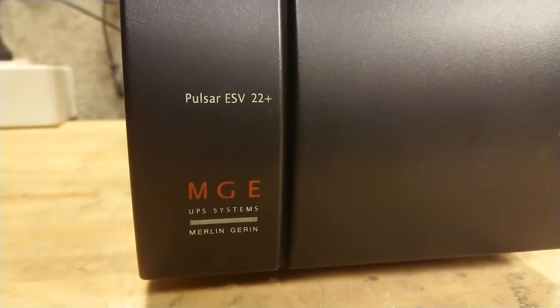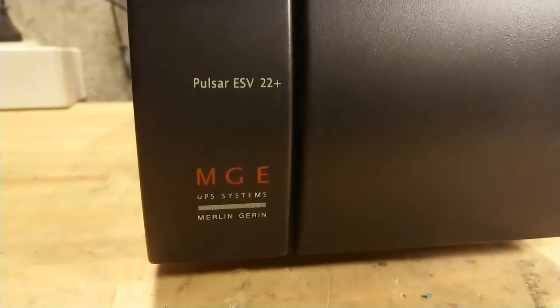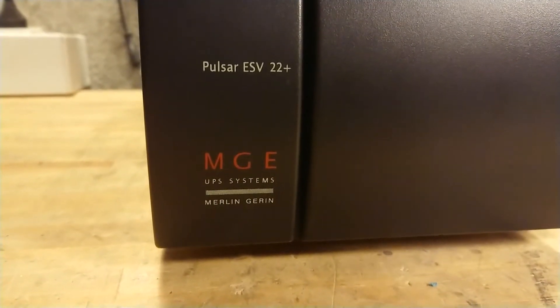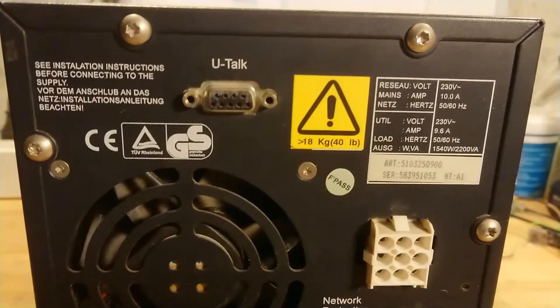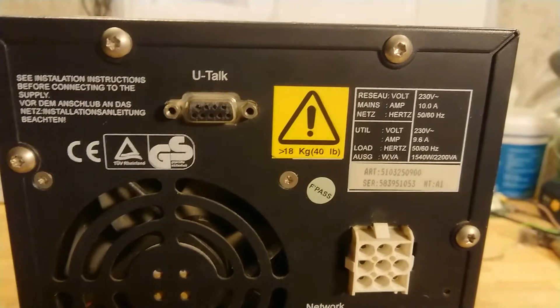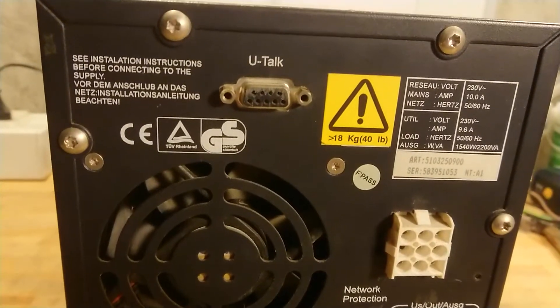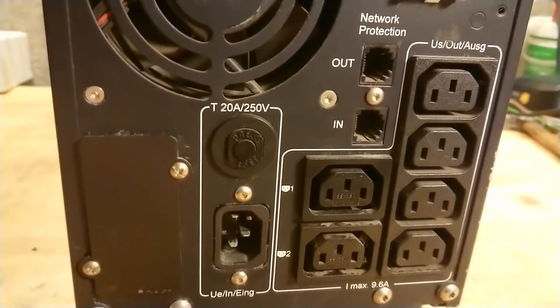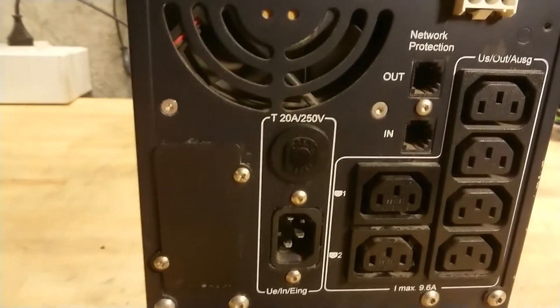Here we can see the model number. It's a Merlin Gerin Pulsar ESV 22+. The 22+ is the kVA rating, which in this case is 2.2. If we take a look at the back of the unit, you can see the marking plate. It's rated for 2.3kW input. There is a serial port, probably some Merlin Gerin protocol. It has network protection input/output, then six outputs and a single input with a small circuit breaker.